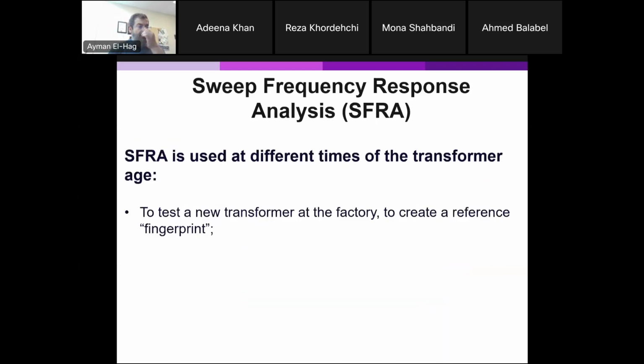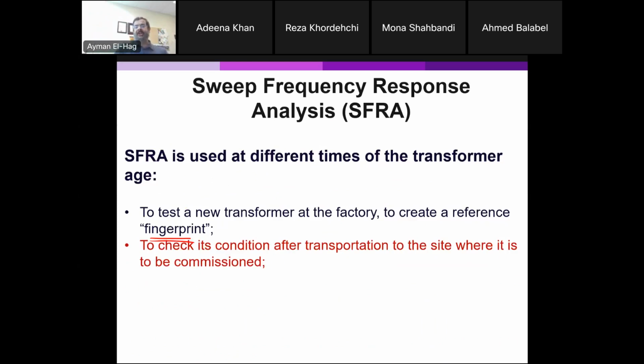Now, why do we use the SFRA? First, you have to have a signature. When the transformer is manufactured at the factory, you have a fingerprint, so you keep that fingerprint. Then you use that fingerprint to compare when you scan the transformer at a different condition. It could be, for example, after transportation, when you transport the transformer from point A to point B, the vibration and movement, especially the core, might move, so you need to take another signature. If they are matching, then there is no issue. If they are not matching, then you will know something happened inside the transformer.